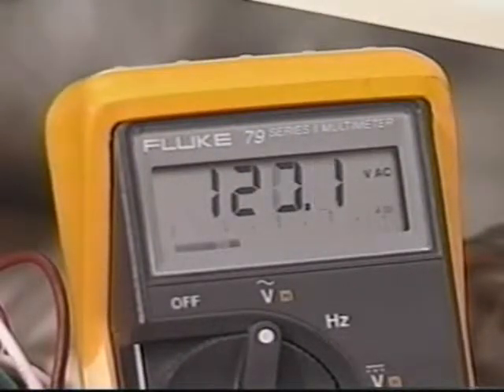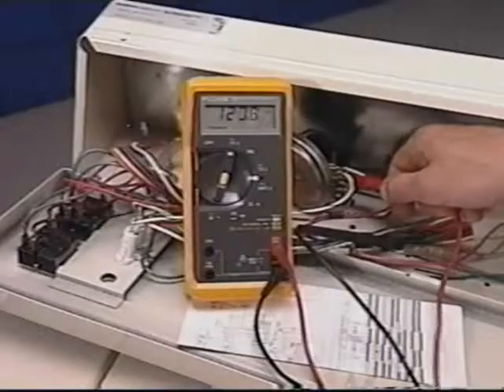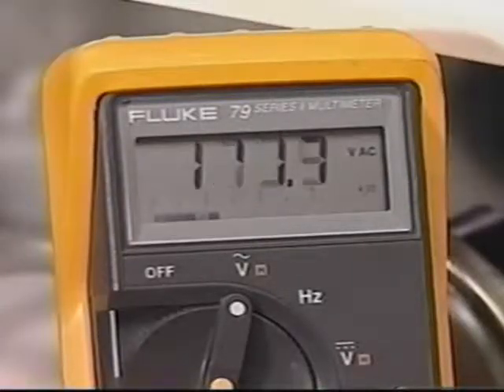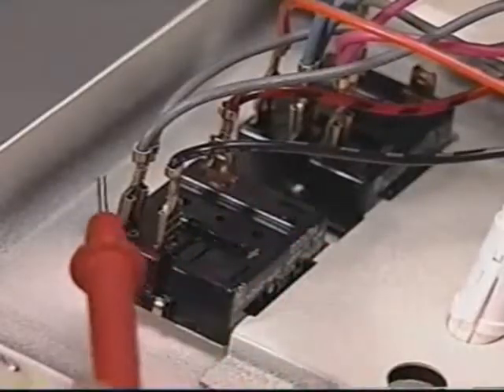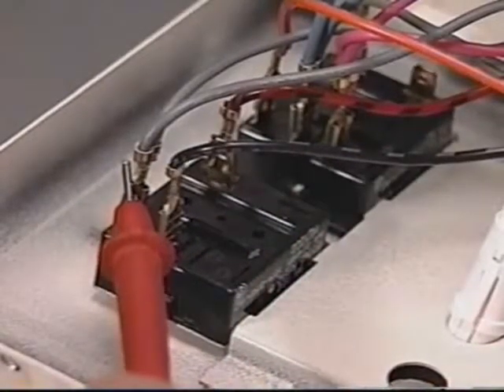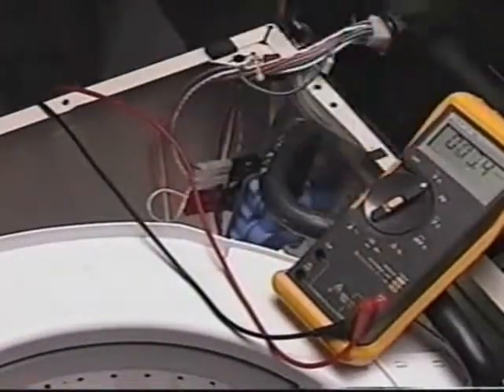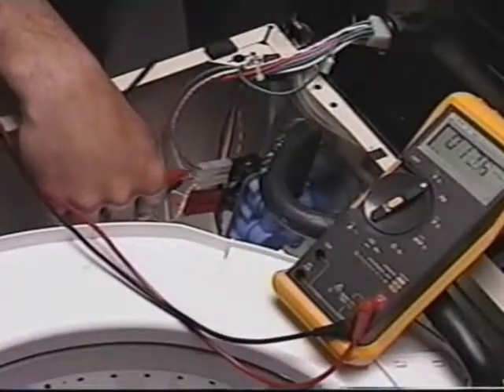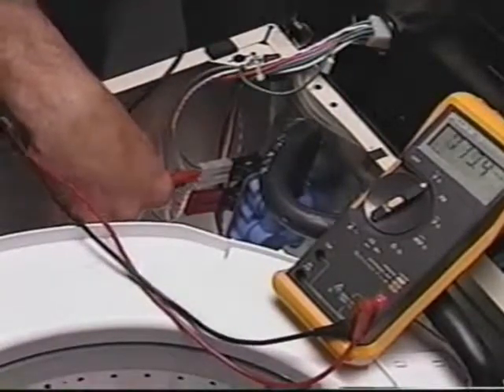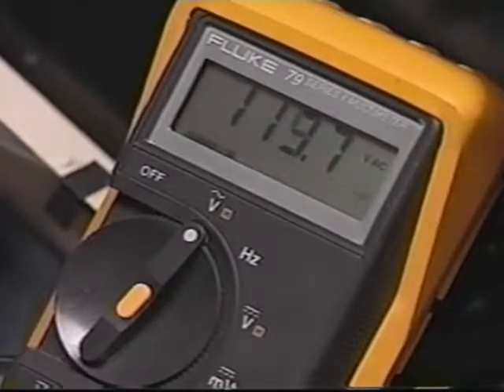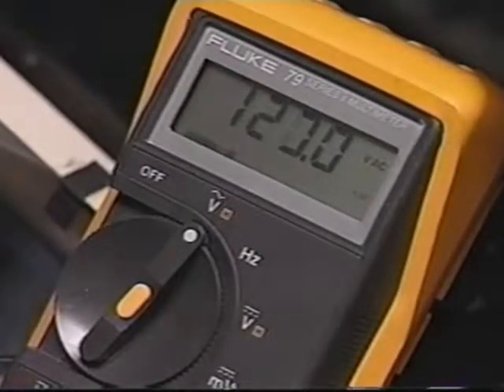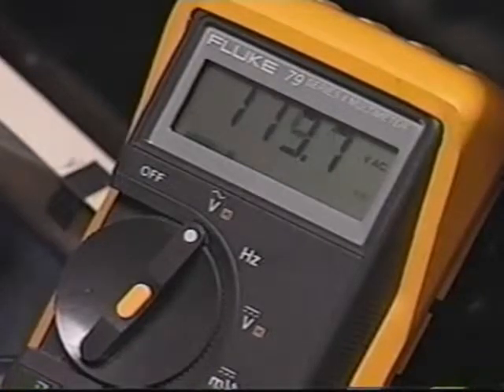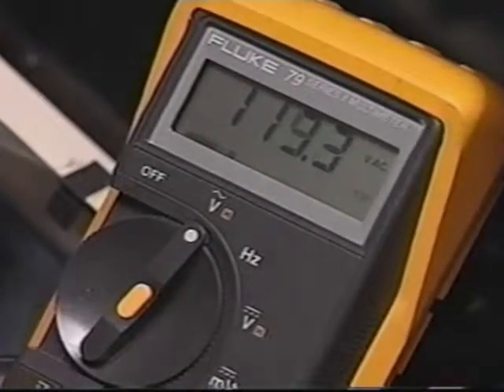Line 1 is present at both terminals, indicating that the switch is closed and our problem is further on in the circuit. Check for line 1 voltage at L2 on the temperature selector. With the switch set on cold, check for line 1 voltage at terminal C. Now that we are at the load in the circuit, we will test across the coil with a voltmeter. There is voltage when checking across the coil. The windings in the coil could be open. The valve could be mechanically inoperative, or it could be as simple as no water pressure available to the valve.